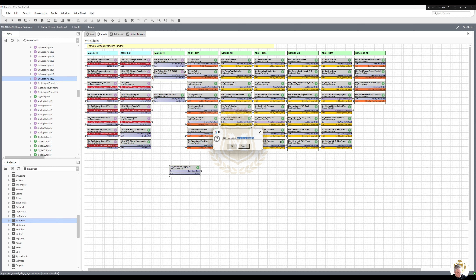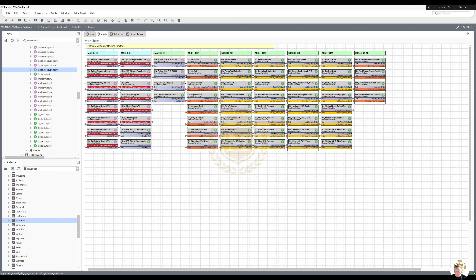They've just got alarms on them, that's that. So DI3 is wrong now, that needs to be duplicate, DI3, and it's post gas supply, delete that, link mark, DI3, that one there, link 2, out there, and then that one is going to BCWS, link from, out, into pulse.